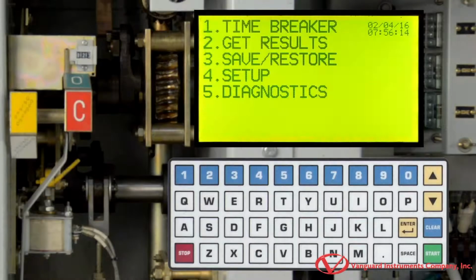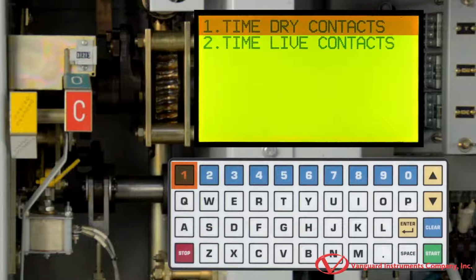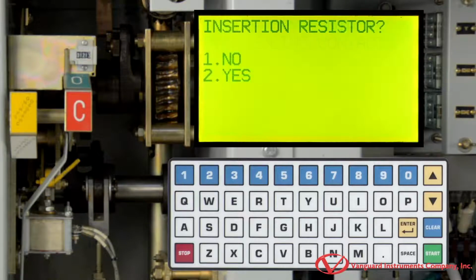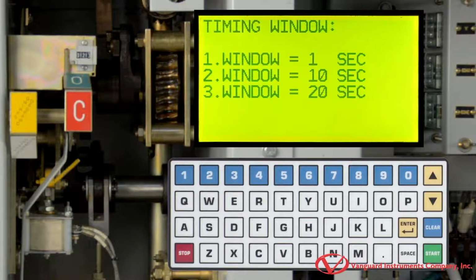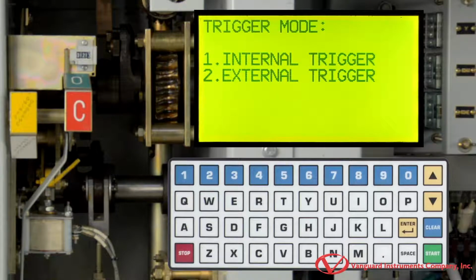To start performing a dual ground test, we will select the time breaker option by pressing the 1 key. Now we will press the 1 key to select time dry contacts. On this screen, we are going to select whether there is an insertion resistor or not, and for this example, we will press 1 for no. On this screen, we will select the timing window. For this example, we will use a 1-second timing window by pressing the 1 key. Now we will select the trigger mode by pressing 1 for internal trigger.